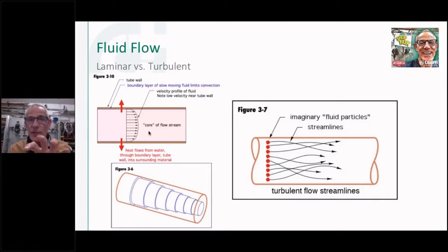And it doesn't transfer heat very well because, you can read right up here, you get this little boundary layer along the outside wall of the tubing. So the heat that's within that water, glycol, whatever the fluid might be that's going through there, isn't in good contact with the surface of the pipe or your radiator, your heat emitter, whatever it might be. So if we're trying to move heat energy out of a fluid stream into a heat emitter, into a pipe, into a radiant slab, whatever it might be, we'd like to have this condition here where all that temperature is contacting the wall of the pipe or the wall of the panel radiator, cast iron radiator, whatever it might be.